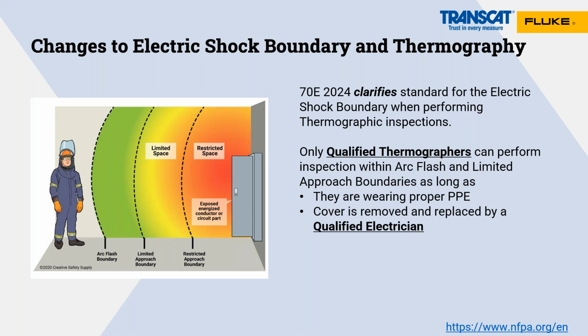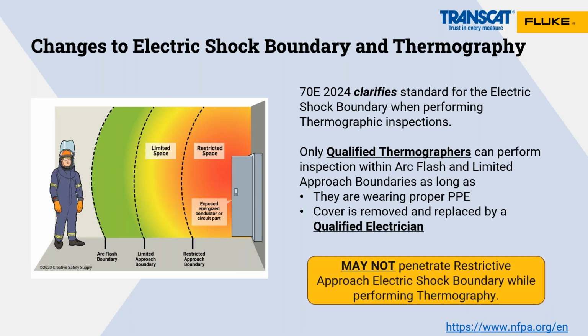Now there is an alternative to this - they're called infrared windows. It's something that we at Fluke do offer. What's a window? It's an arc flash or arc blast rated window - pure crystal that you can mount on a panel. Then I just flip down the cover outside, and I can do this without having to open up the door and have all the heavy PPE gear on. So they're all alternatives to not having to open that panel door.